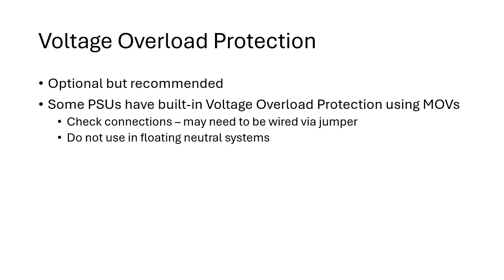So we talked about current overload protection. You can also get voltage overload protection. Some electronic devices are very sensitive to high voltages, so voltage overload protection is built into some power supplies, and the idea is this stops the voltage from getting too high. So if you look at a typical PLC, it's probably nominal 24 volts DC, but with a maximum of 30 volts. So you need to be careful that the voltage from your power supply doesn't exceed 30 volts.